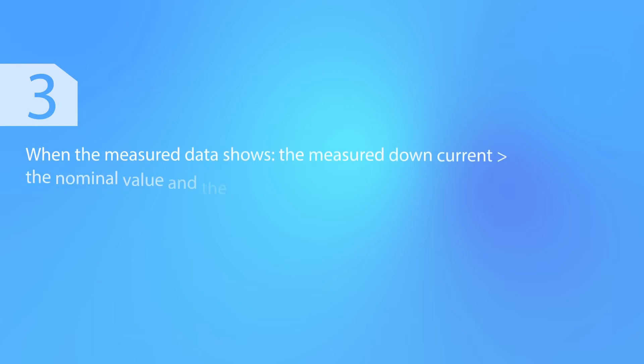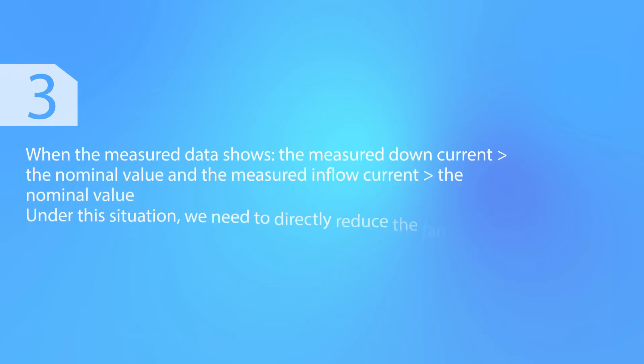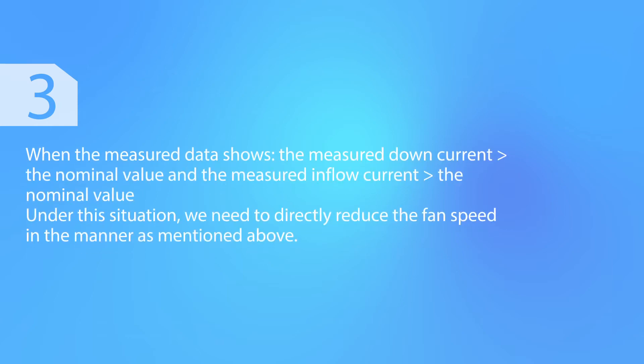When the measured data shows that the measured down current is above the nominal value and the measured inflow current is also above the nominal value, we need to directly reduce the fan speed in the manner as mentioned above.